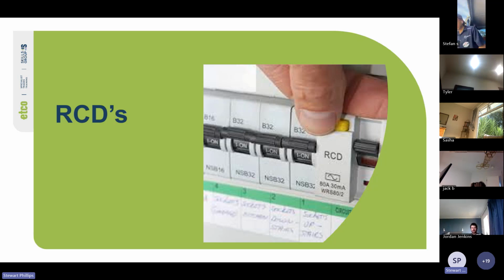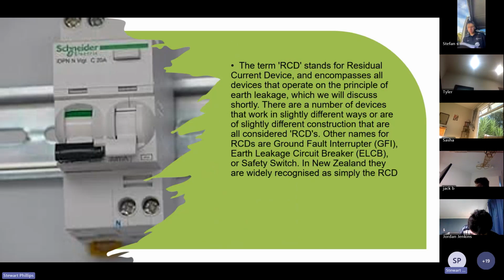Cool. So RCDs or RCCBs. The term RCD stands for residual current device, whereas RCCB stands for residual current circuit breaker, and encompasses all devices that operate on the principle of earth leakage, which we'll discuss shortly. There are a number of devices that work slightly differently, but other names for RCDs are ground fault interrupter or GFI, which is what Americans call it, earth leakage circuit breaker, ELCB, or safety switch. In New Zealand, we widely recognize it simply as RCD.